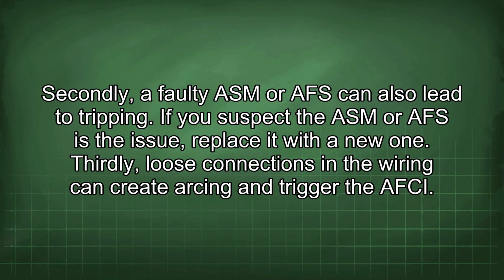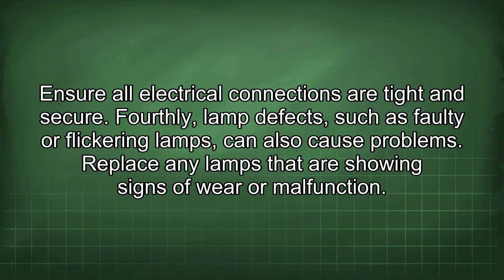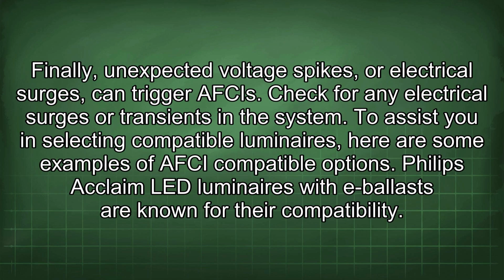Thirdly, loose connections in the wiring can create arcing and trigger the AFCI. Ensure all electrical connections are tight and secure. Fourthly, lamp defects, such as faulty or flickering lamps, can also cause problems. Replace any lamps that are showing signs of wear or malfunction. Finally, unexpected voltage spikes or electrical surges can trigger AFCIs. Check for any electrical surges or transients in the system.